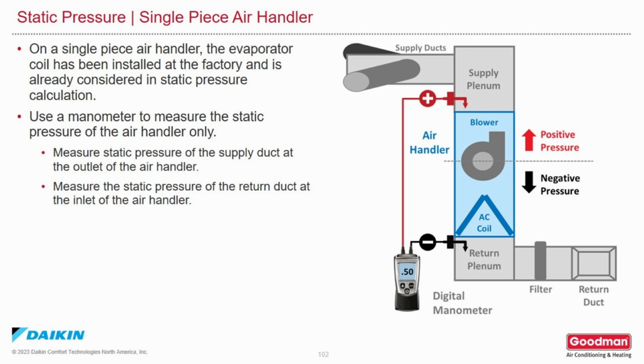Getting static pressure readings on a single-piece air handler, the evaporator coil has been installed at the factory and is already considered in the static pressure calculation. Use a manometer to measure the static pressure of the air handler only. Measure the static pressure of the supply duct at the outlet of the main air handler in the supply plenum. Measure the static pressure of the return duct at the inlet of the air handler, downstream of the filter.